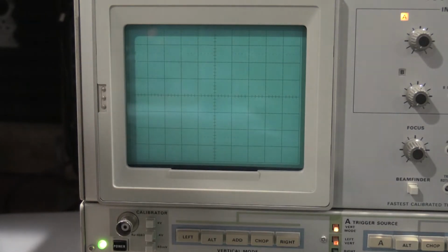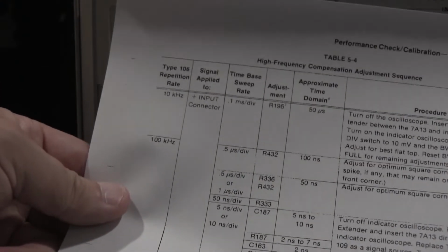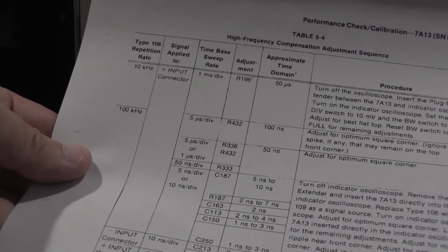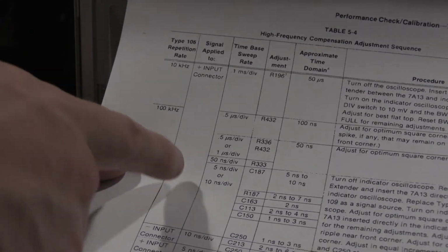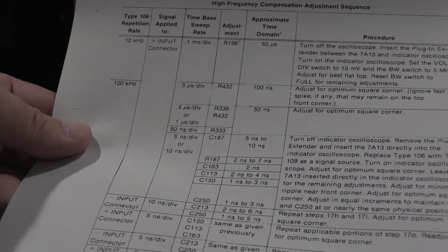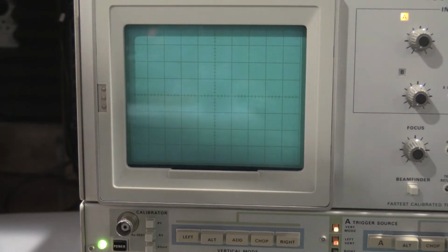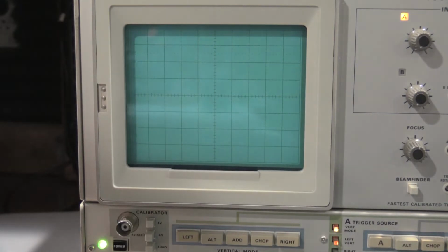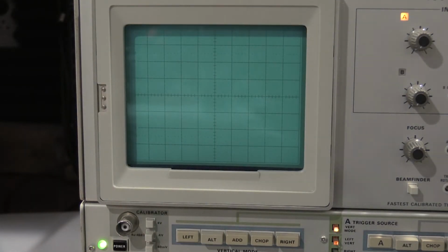the high frequency compensation actually does not care about what the ranges are. Due to this table in 5.4, which is the high frequency adjustment, it's adjusting the connectors. You're not adjusting each attenuator like you're doing with a scope, and the adjustments are only done with a 106 on the front end. So I can use a type 106 to hit the highest ranges, because that's what you'd actually adjust them with anyway.